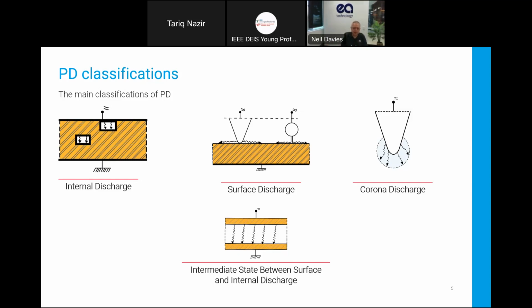However, if we put that corona discharge inside a sealed box in metal clad switchgear, then what's happening there is that the byproducts of the discharge, so the nitrous oxides, the ozone, will combine with the moisture, produce nitric acid, and start attacking other insulation, and typically transfer over to the surface discharge, and that's where it causes problems.